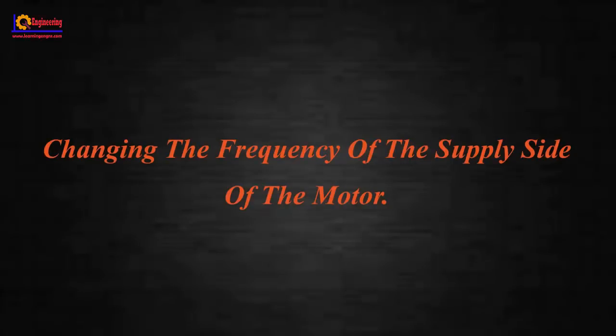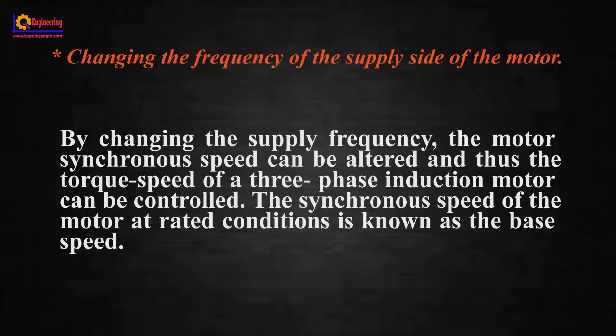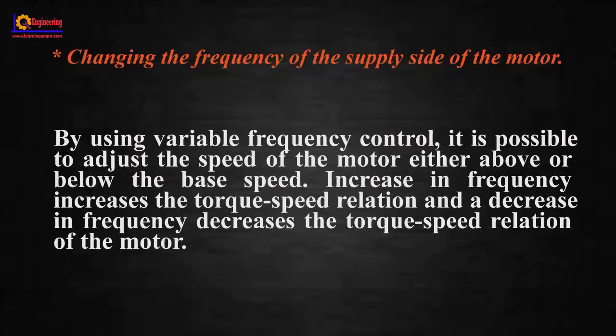Changing the frequency of the supply: by changing the supply frequency, the motor synchronous speed can be altered and thus the torque-speed of a three-phase induction motor can be controlled. The synchronous speed at rated condition is known as the base speed. By using variable frequency control, it is possible to adjust the speed of the motor above or below the base speed. Increase in frequency increases the torque-speed relation and decrease in frequency decreases the torque-speed relation.